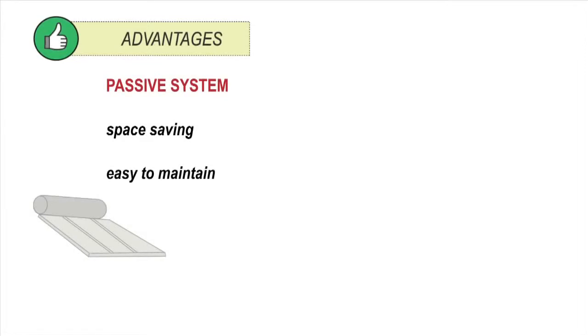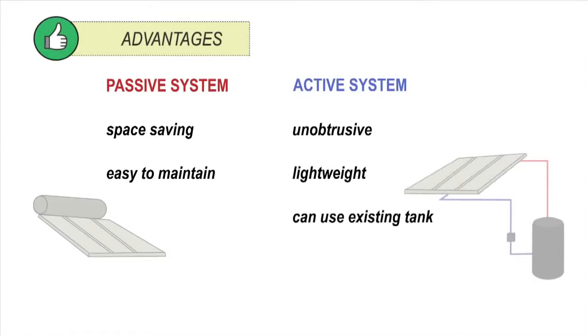Each type of system has advantages. A passive system is space-saving and is easy to maintain with no moving parts. An active system is unobtrusive, lightweight, can use an existing tank and the tank can be located closer to where hot water is used, reducing heating loss in pipes. But the pump uses some energy.